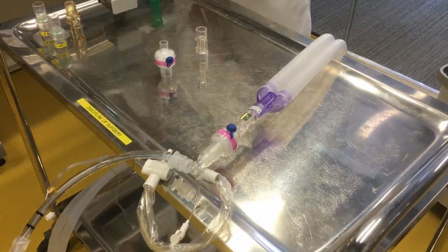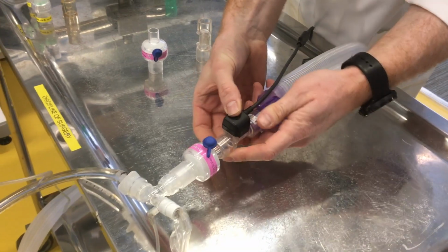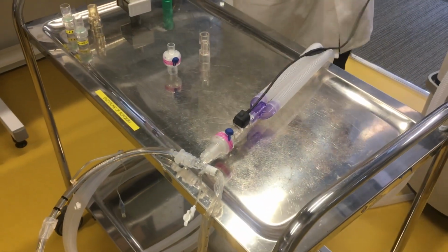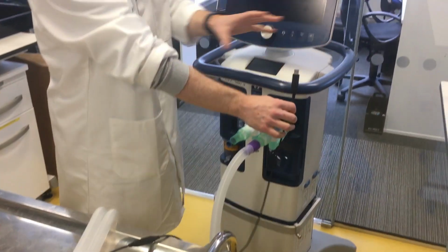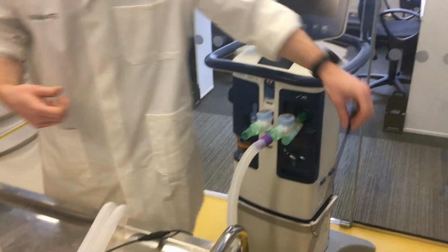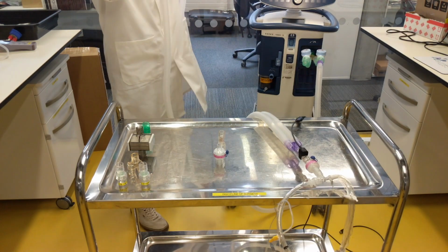Now this flow sensor is where we are going to connect the individual patient displays. That will be done via a cable here with a clip. So that goes on like so, and then this cable is routed back along the breathing circuit and will be attached to a small display on either side per patient with the patient's individual tidal volumes and pressures and PEEPs. So I'll leave that there, and we will start to attach our second patient circuit.